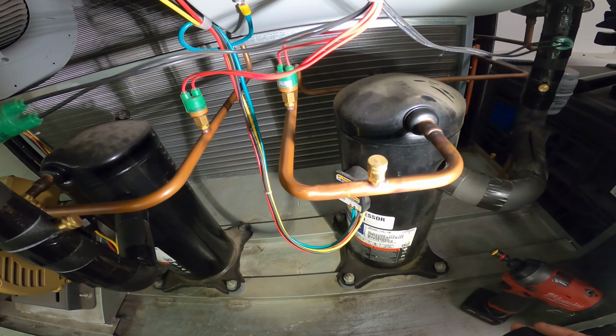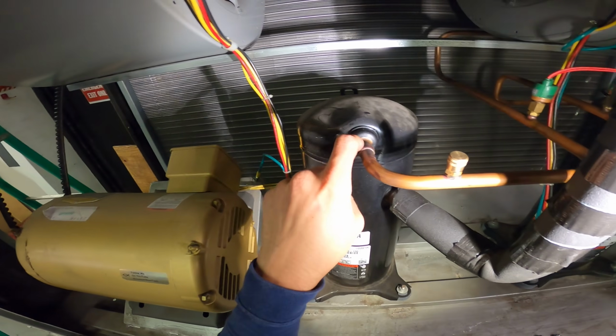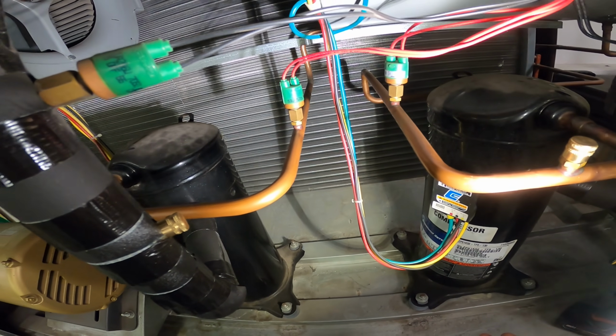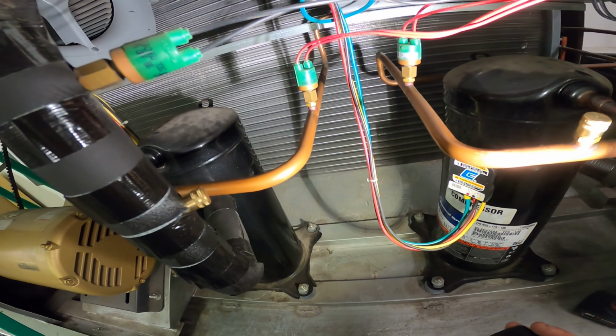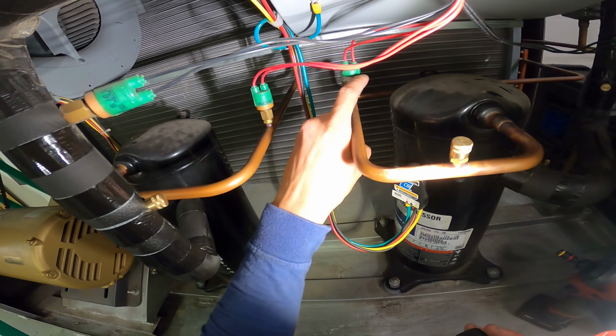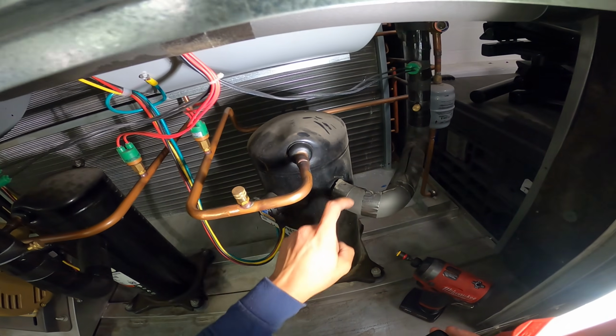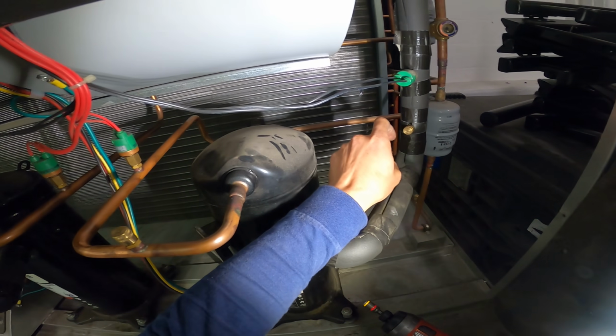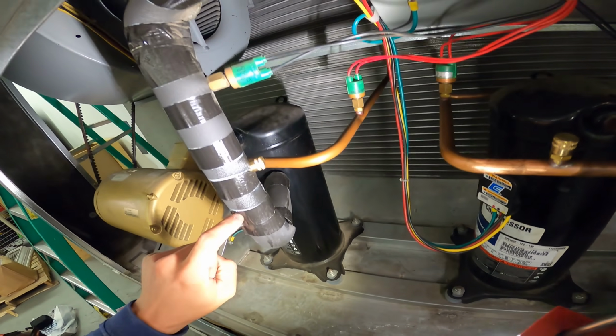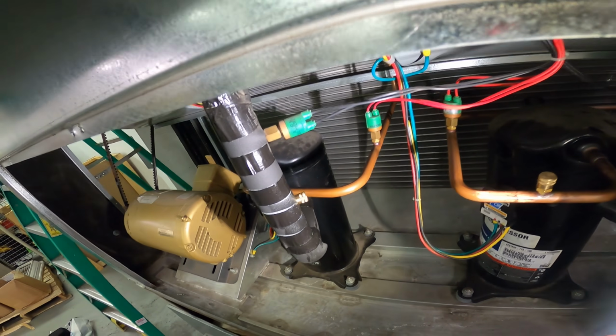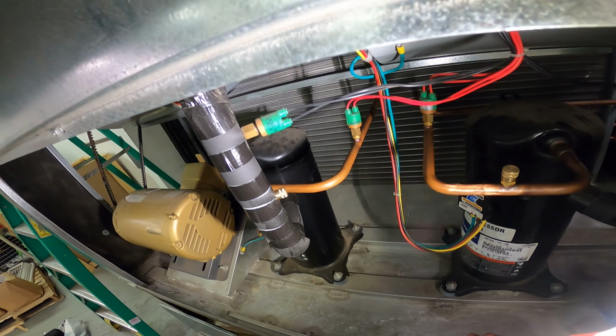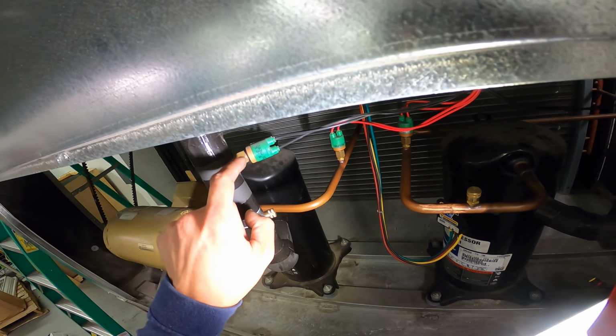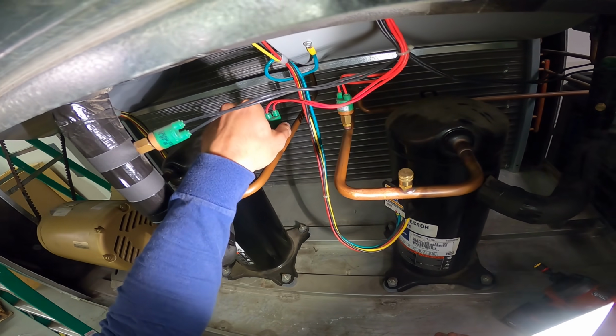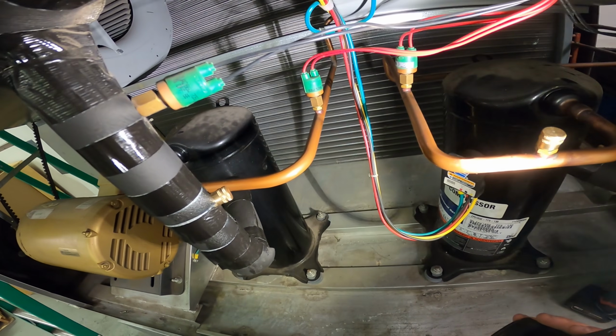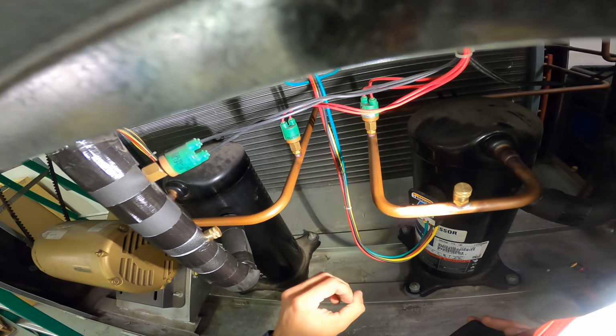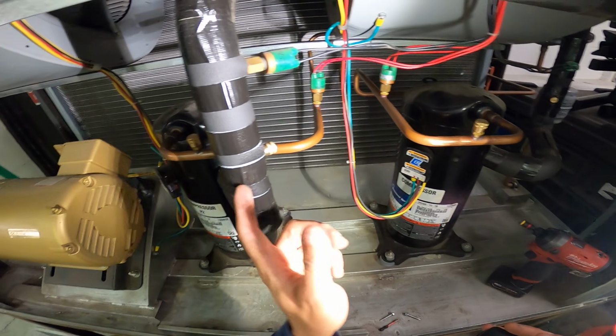Here we have one pressure control, and it's red, two wires. We follow this discharge line, we have another control, and it's two wires. So what does that tell me? Since I know it's the discharge side, and the discharge side is on the high side, this is our high pressure control. Next, we follow the larger pipe, which is the suction line. And what do we have here? We have more pressure controls, one on this compressor and one on this one. And since I know the suction line is on the low side of the system, this is our low pressure control. If the system runs on low pressure, then this circuit will open and shut down your compressor. If your system is running on high pressure, once it reaches a predetermined value, depending on the refrigerant in the system, it's going to open the circuit and shut off your compressors to protect them. So these are safety controls.